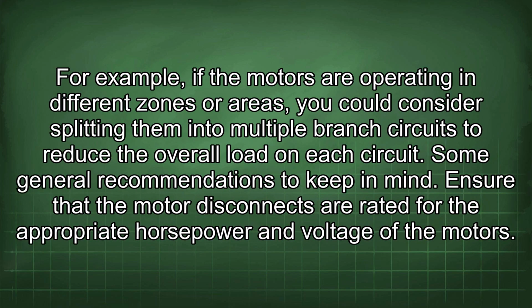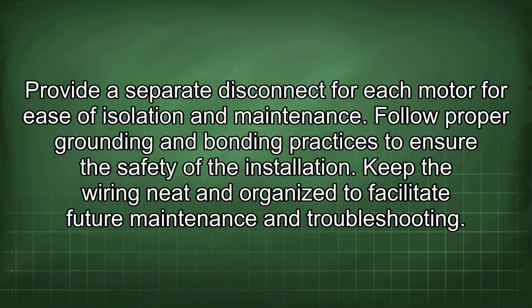For example, if the motors are operating in different zones or areas, you could consider splitting them into multiple branch circuits to reduce the overall load on each circuit. Some general recommendations to keep in mind. Ensure that the motor disconnects are rated for the appropriate horsepower and voltage of the motors. Provide a separate disconnect for each motor for ease of isolation and maintenance.